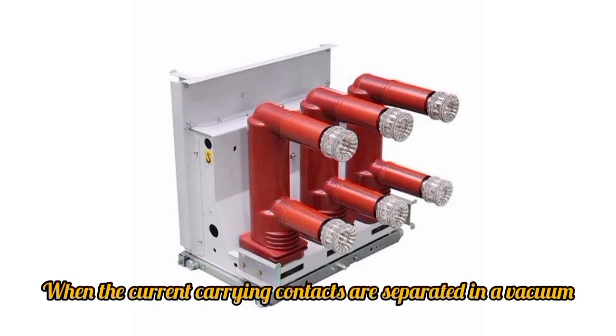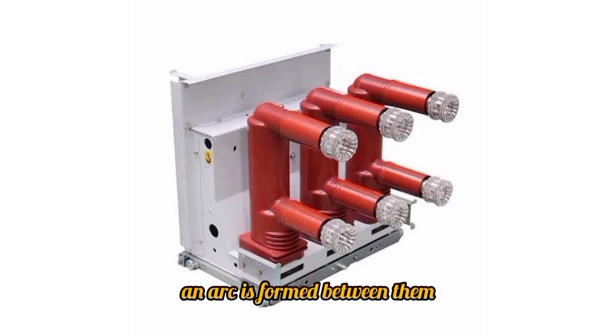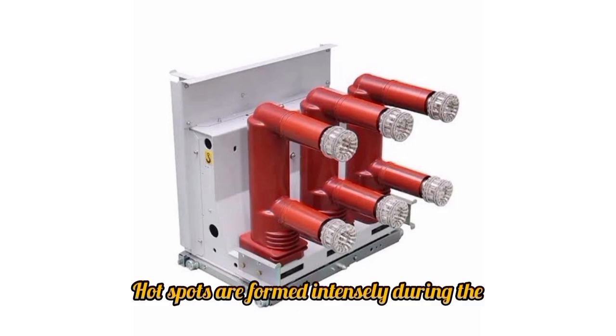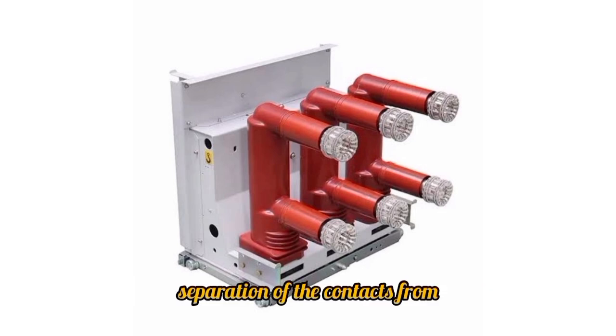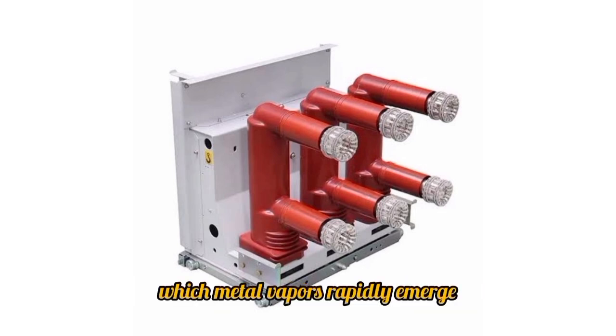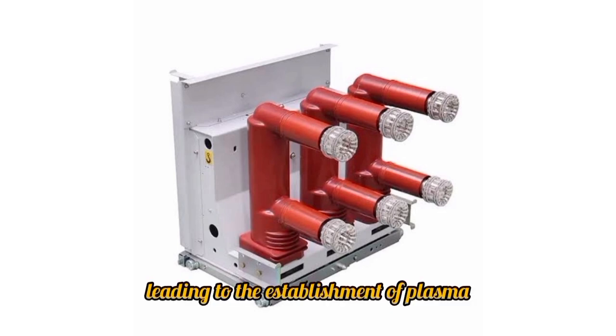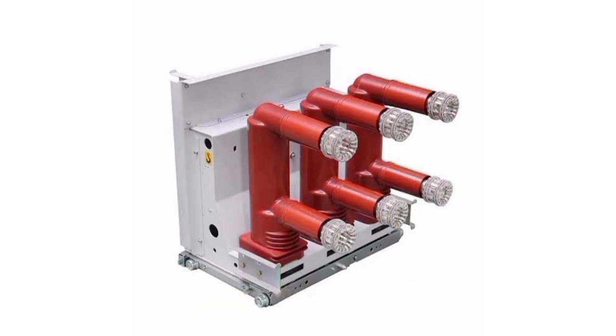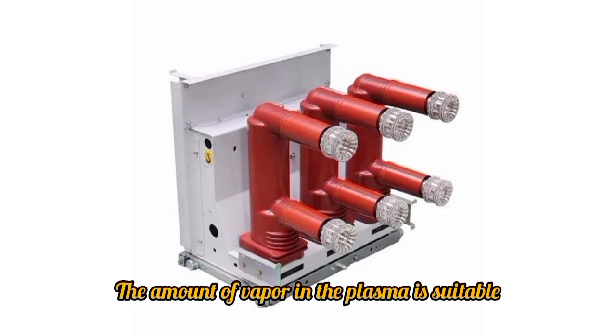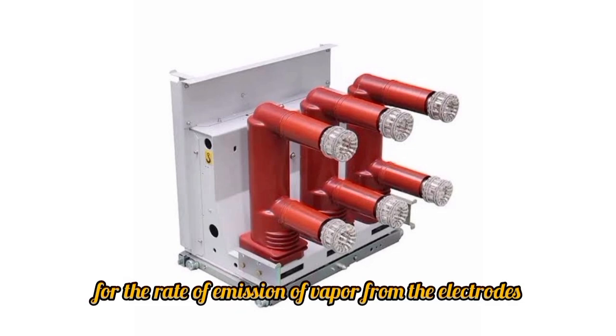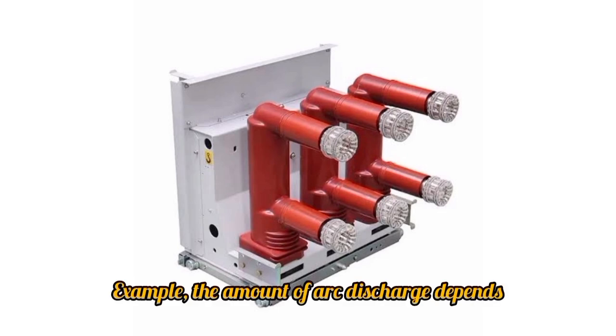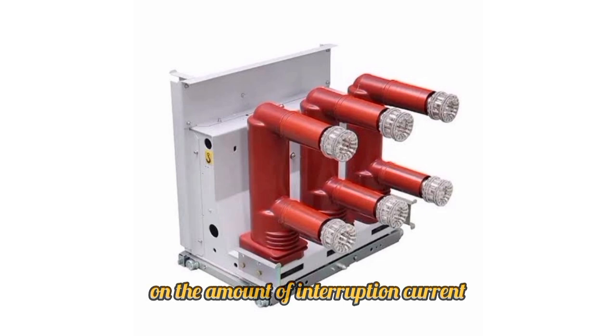When the current-carrying contacts are separated in a vacuum, an arc is formed between them. Hot spots are formed intensely during the separation of the contacts, from which metal vapors rapidly emerge, leading to the establishment of plasma. The amount of vapor in the plasma is suitable for the rate of emission of vapor from the electrodes. For example, the amount of arc discharge depends on the amount of interruption current.